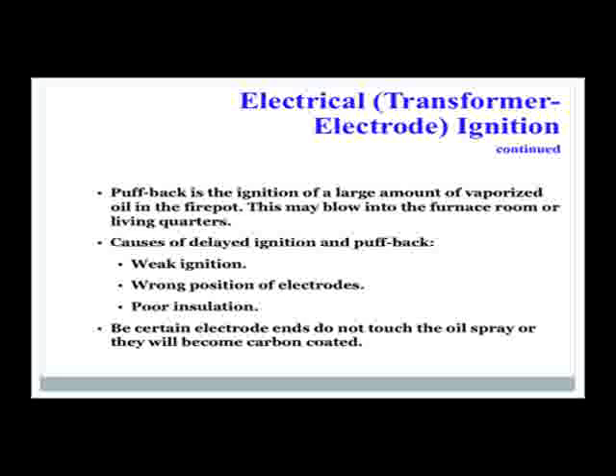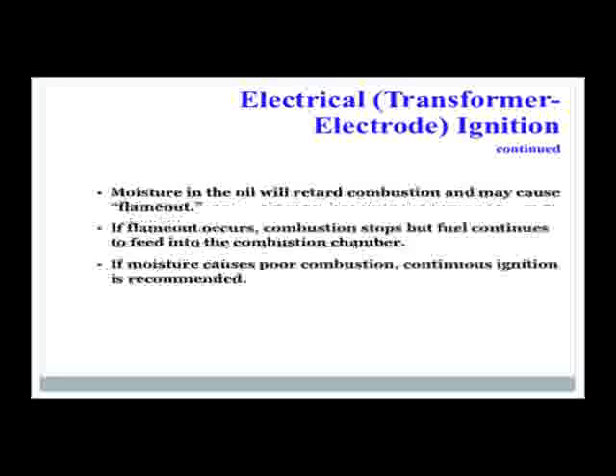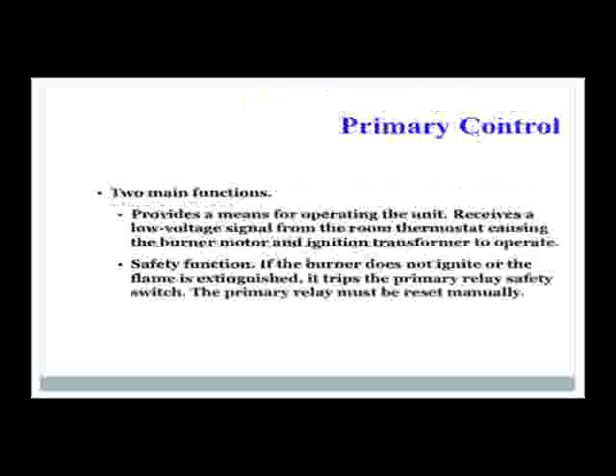Puffback is the ignition of a large amount of vaporized oil in the fire pot or the chamber. This may blow the furnace room door open or into the living quarters. The causes of delayed ignition and puffback are weak ignition, wrong position of the electrodes, and poor insulation. Be certain electrode ends do not touch the oil spray or they will become carbon coated. Moisture in the oil will retard combustion and may cause flame out. If flame out occurs, combustion stops, but fuel continues to feed into the combustion chamber. If moisture causes poor combustion, continuous ignition is recommended.